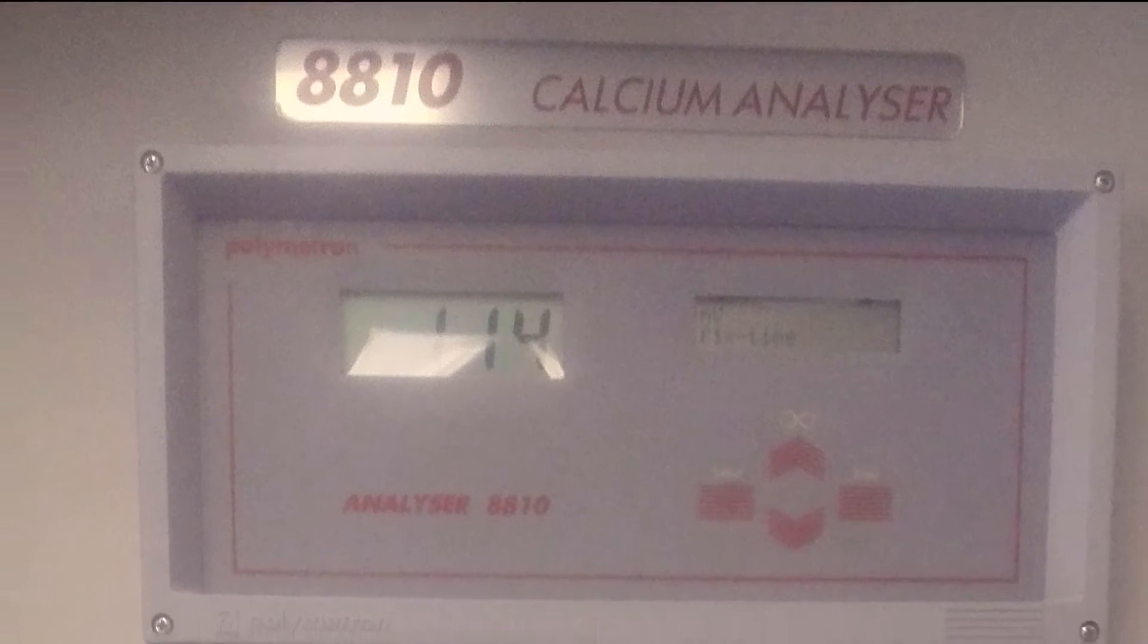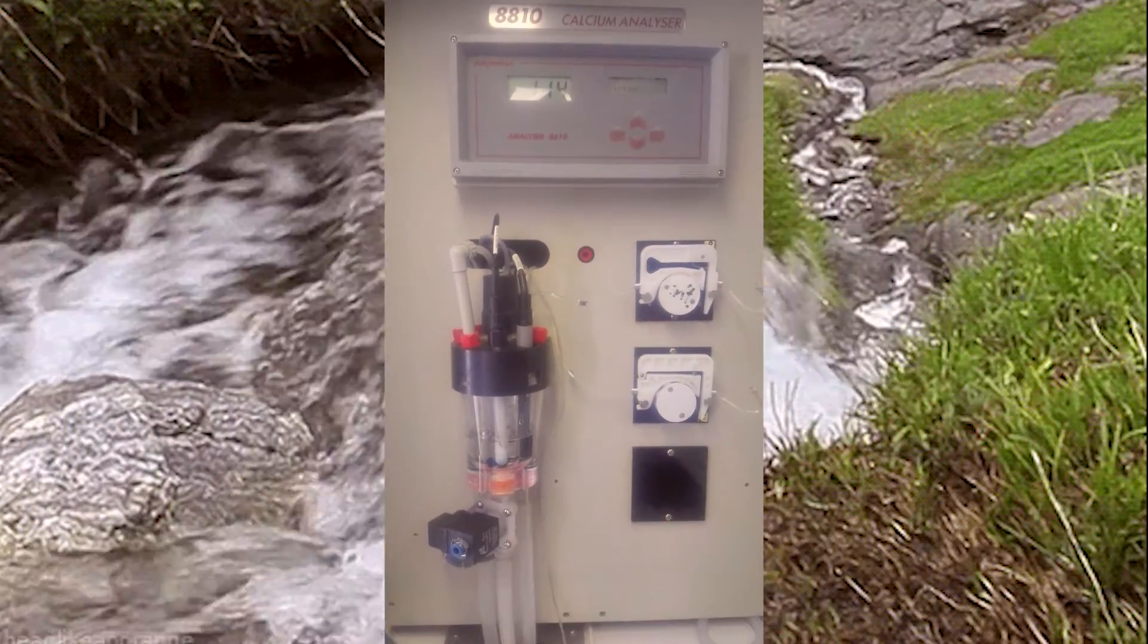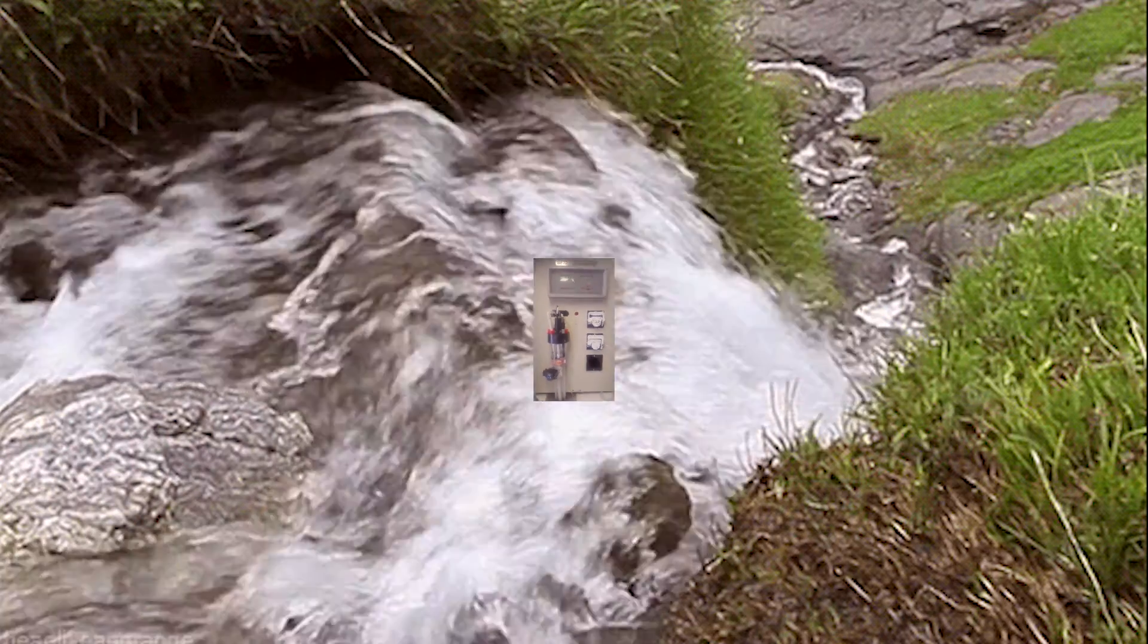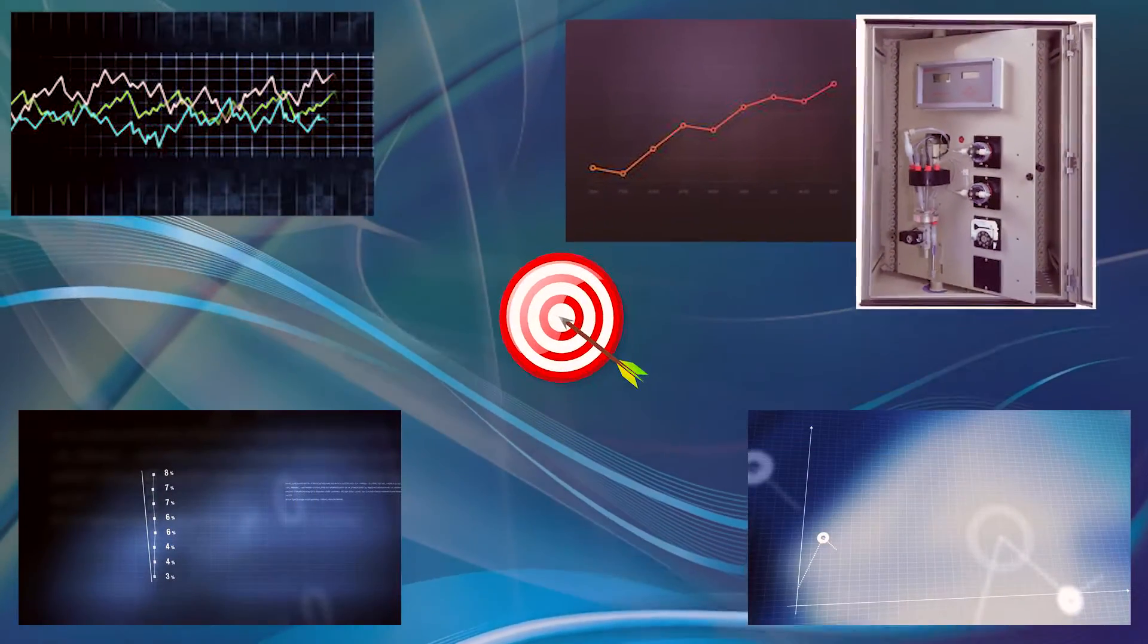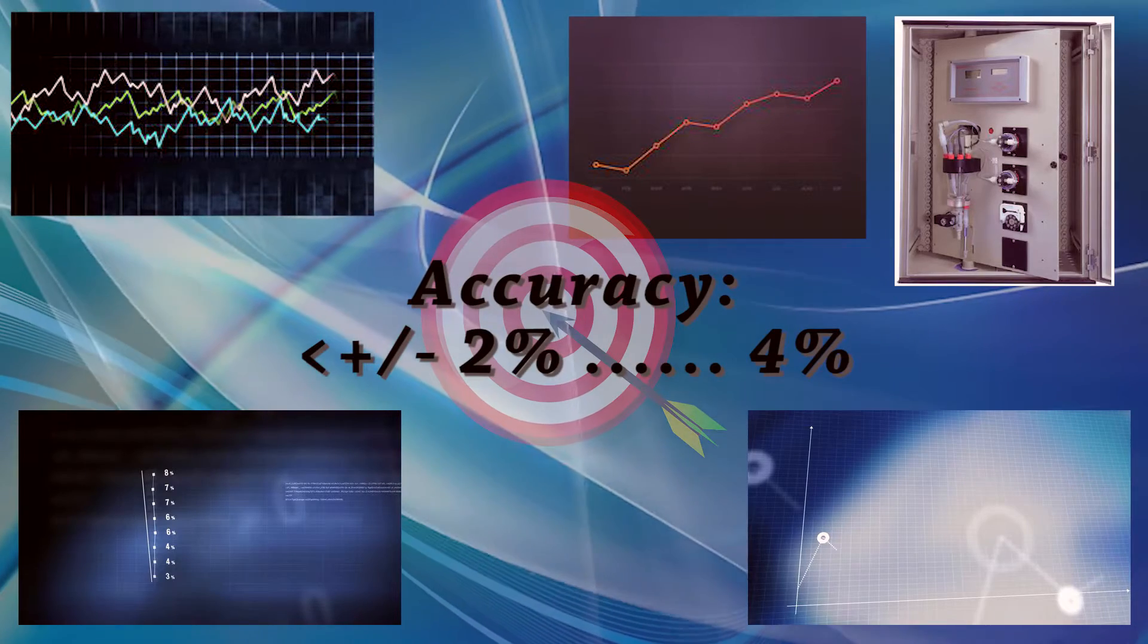But I will discuss the 8810 especially to measure calcium concentration in running stream of potable water. This analyzer is reliable in terms of analysis. It has plus minus 2 to 4% accuracy.